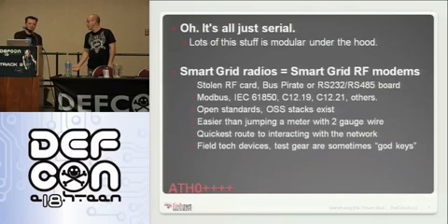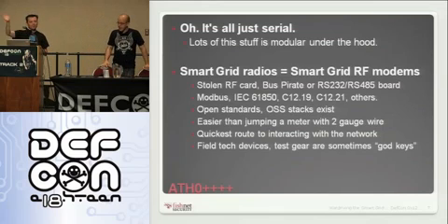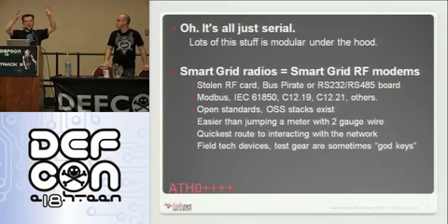Yeah, and that C1219 protocol has an entire stack of messages that indicate different things that happen to the meter. This voltage changed, this thing changed, or this line was unplugged, or whatever. But all of those events create more traffic on the network, which means buying more relays for that network, which means creating more traffic. You've got to buy more gear and rescope how many collection points you have versus how many devices, so they're kind of off by default, in our experience.